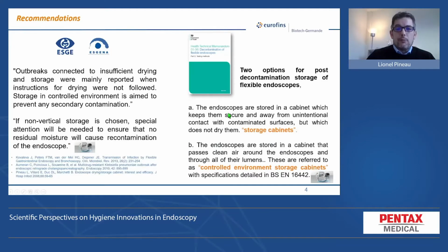In the ESGE guideline published in 2018, experts consider that outbreaks connected to insufficient drying on storage were mainly reported when instructions for drying were not followed, and that storage in a controlled environment should prevent any secondary contamination. They also indicate that if non-vertical storage is chosen, special attention will be needed to ensure that no residual moisture will cause recontamination of the endoscope. So all experts agree on the fact that drying is really a key point, and that some things need to be done to eliminate water from the endoscope channel.